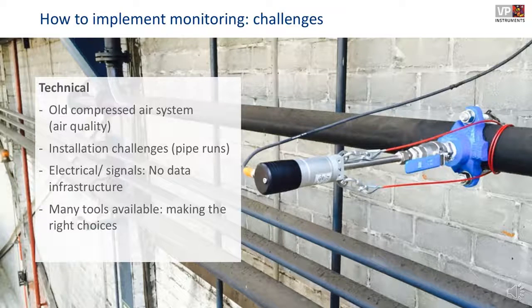Then there are technical challenges. We've encountered old compressed air systems with poor air quality, or old rusted pipes where putting in a flow meter was hard because you could stick your finger through the outer wall. And talking about rust, how do we know what the inner pipe surface looks like? It could be a moon-like landscape in there from years of corrosion. This all relates to measuring something with a flow meter and not being sure if it's the right value. We've seen pipes completely clogged with cement, or even fat from sauce plants or butter manufacturing plants.